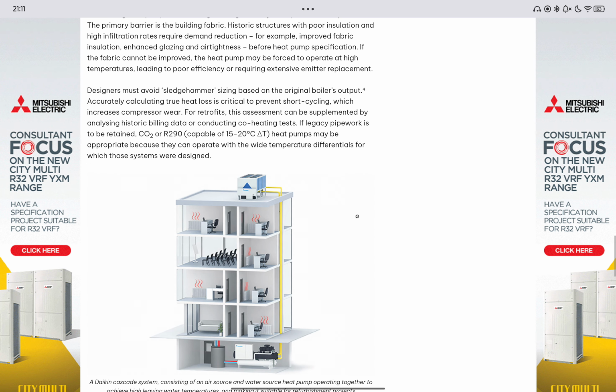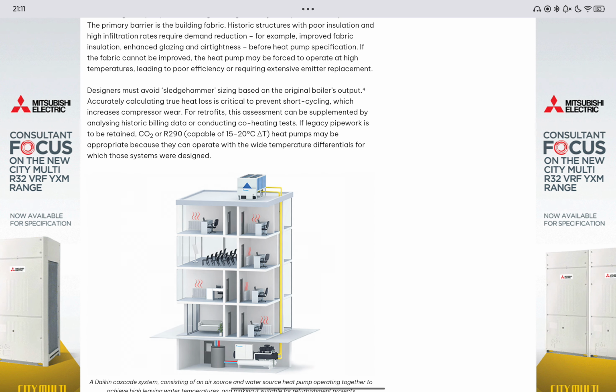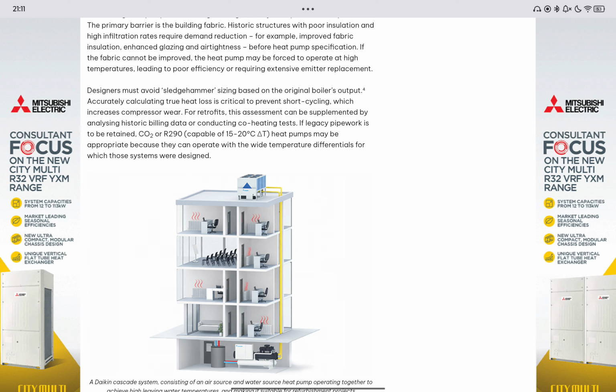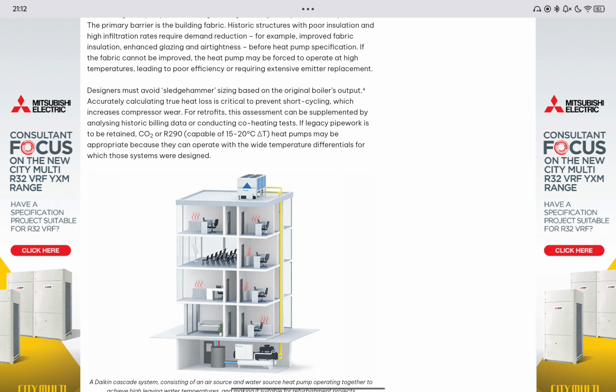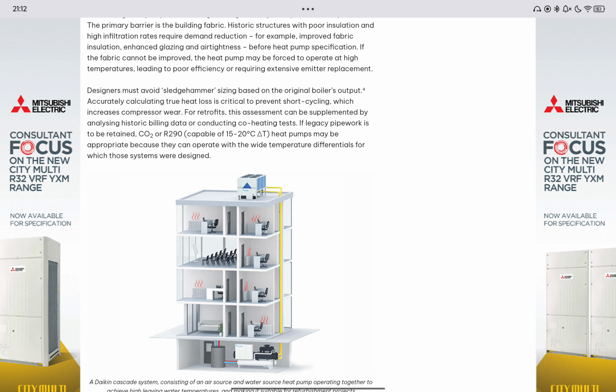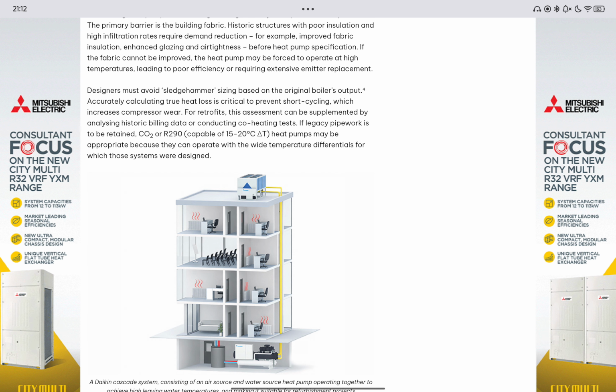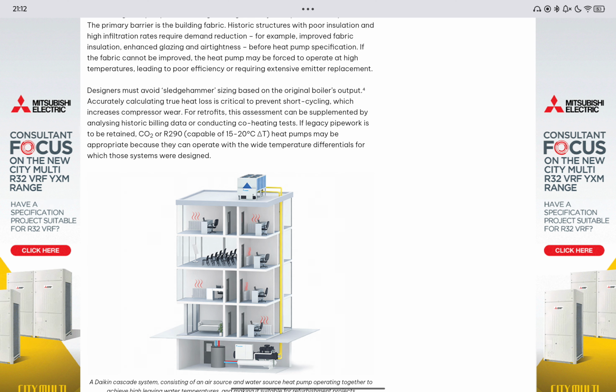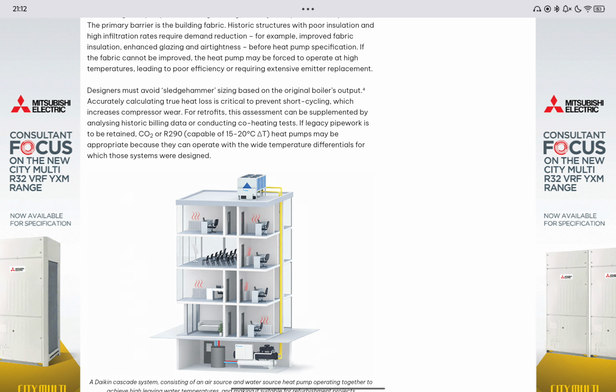Designers must avoid sledgehammer sizing based on the original boiler's output. Accurately calculating true heat loss is critical to preventing short cycling, which increases compressor wear. For retrofits, this assessment can be supplemented by analysing historic billing data or conducting co-heating tests. If legacy pipework is to be retained, carbon dioxide or CO2 or R290 capable of 15 to 20 degrees C delta T heat pumps may be appropriate because they can operate with wide temperature differentials for which those systems were designed.